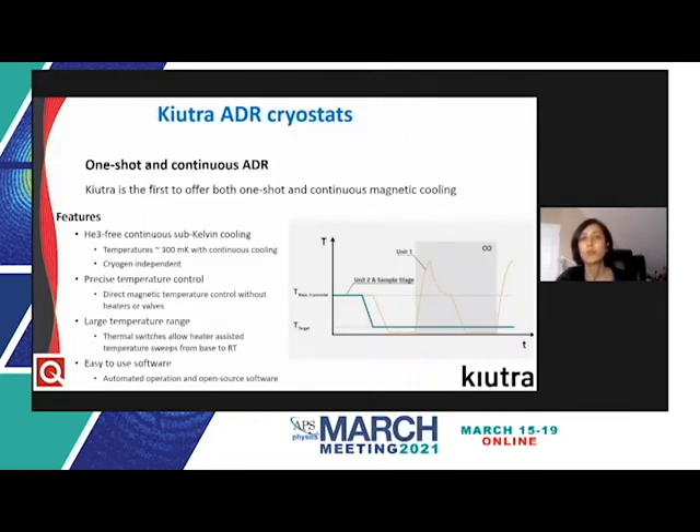Kiutra is the first to offer both single-shot as well as continuous ADR cryostats. By combining multiple ADR units, these systems sustain temperatures as low as 300 millikelvin continuously. The first ADR unit shuttles between the low temperature stage and the thermal bath, while the second unit provides sub-Kelvin temperatures continuously to the sample stage. This direct magnetic temperature control without heaters or valves allows extremely precise regulation, and every ADR system features heater-assisted temperature ramps from sub-Kelvin to room temperature without warming the entire system. The absence of circulating gas and cryoliquids allows automation via open source Python-based software.